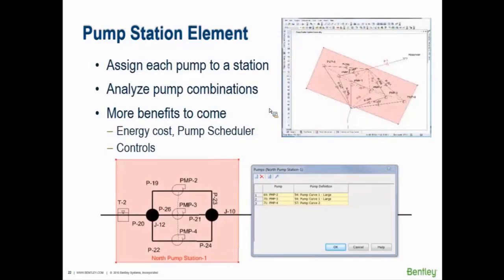Pump station elements were added in Select Series 5 or 6 for V8i and are available in the Connect Edition. You draw a polygon around the pump station and associate all elements inside it to that polygon. This lets you analyze different pump combinations, look at energy costing at the pump level, and modify controls for the entire pump station — giving you a higher-level view of pump operations.